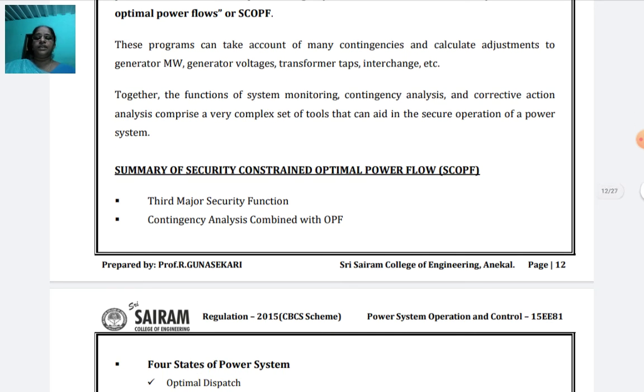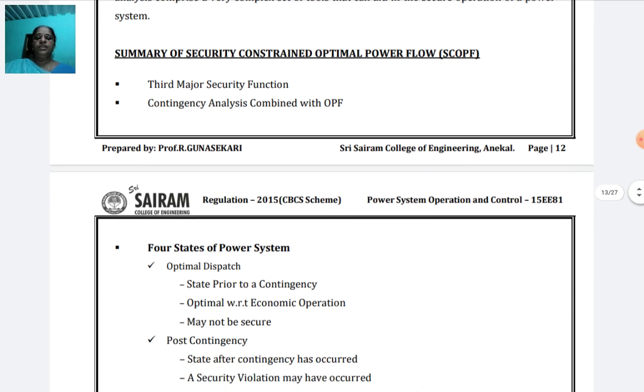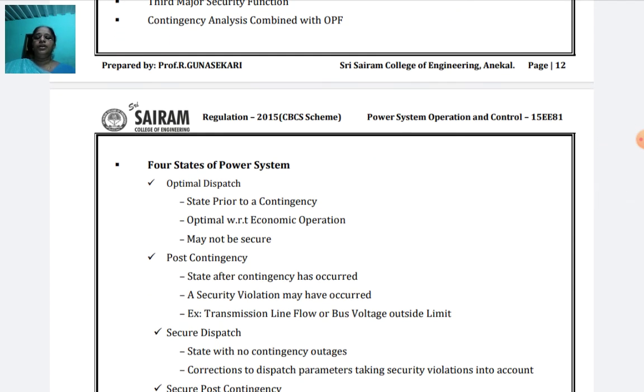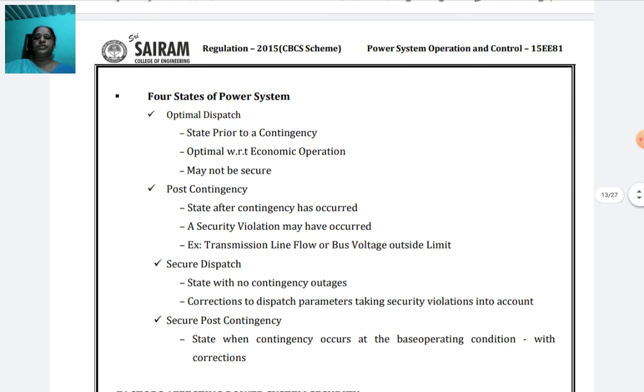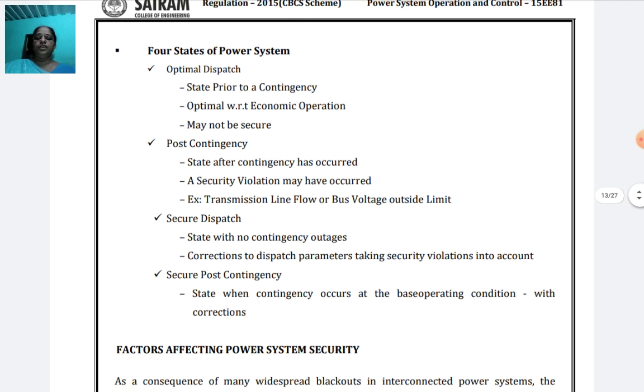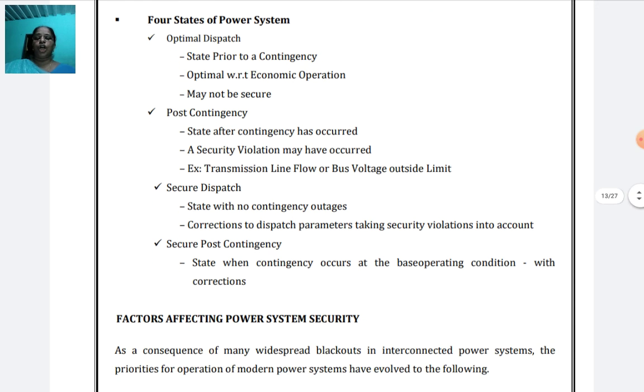Second one is contingency analysis combined with optimal power flow. In this case, four states are there. One is the optimal dispatch state. In the optimal dispatch state, the state prior to a contingency, optimal with respect to economic operation, may not be secure. Second one is post contingency: the state after a contingency has occurred, where a security violation may have occurred, for example transmission line flow or bus voltage outside limit. Third state is secure dispatch: the state with no contingency outages, with corrections to dispatch parameters taking security violations into account. Fourth is the secure post contingency state.